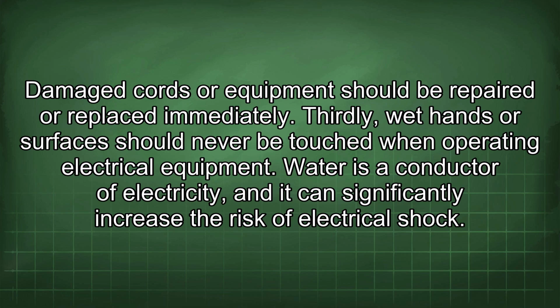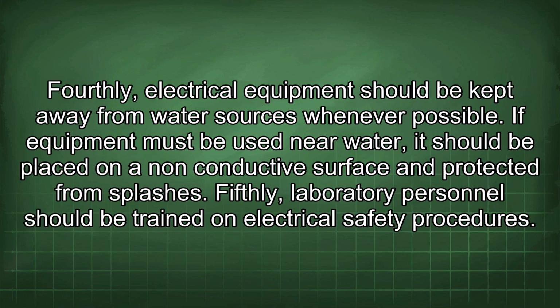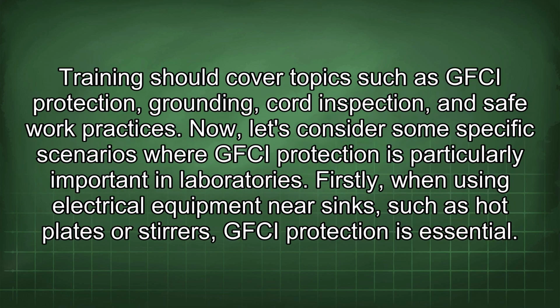Thirdly, wet hands or surfaces should never be touched when operating electrical equipment. Water is a conductor of electricity, and it can significantly increase the risk of electrical shock. Fourthly, electrical equipment should be kept away from water sources whenever possible. If equipment must be used near water, it should be placed on a non-conductive surface and protected from splashes. Fifthly, laboratory personnel should be trained on electrical safety procedures. Training should cover topics such as GFCI protection, grounding, cord inspection, and safe work practices.